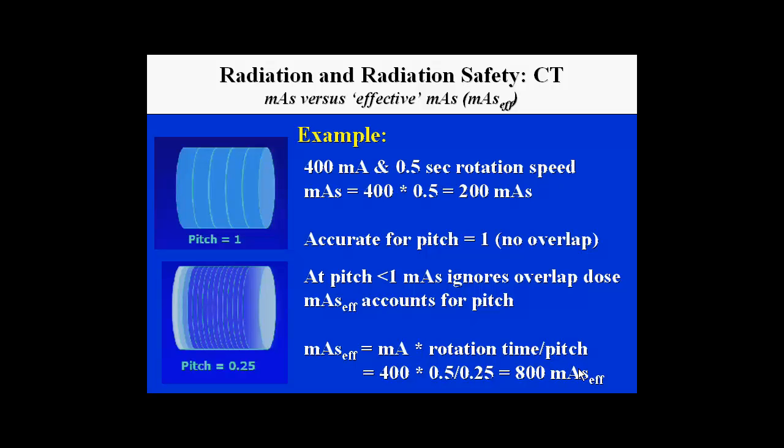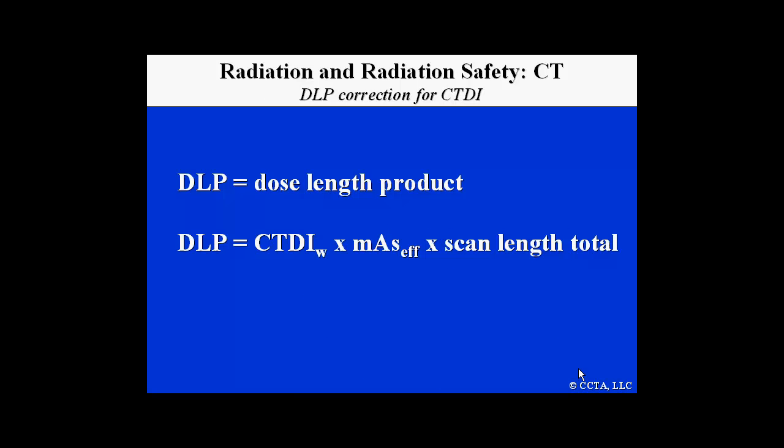Therefore, when we go to a pitch one-quarter the standard pitch, we increase the radiation dose significantly. The other important consideration is not only the dose within a particular area, but the length of the scan. This produces something called the dose length product, which uses the CTDI result and the mAs effective, multiplied by the total scan length.